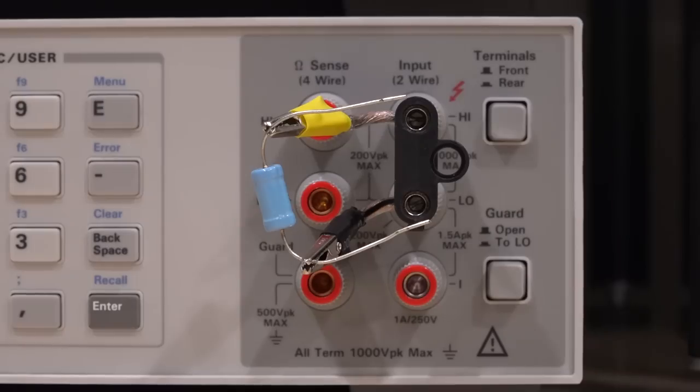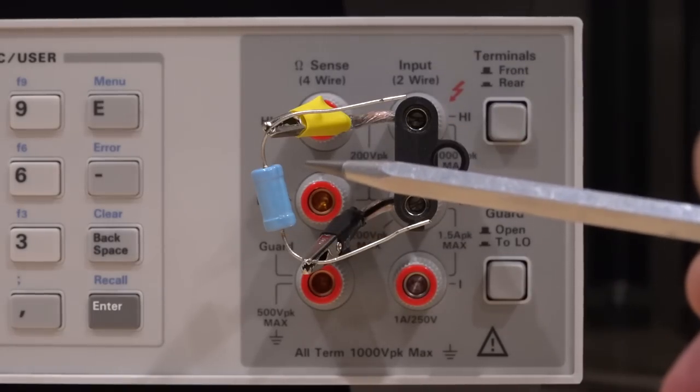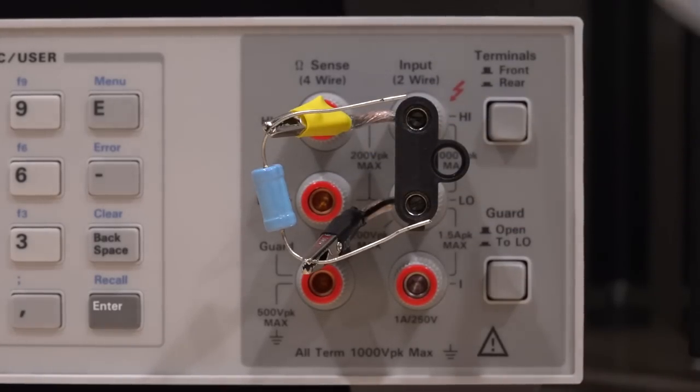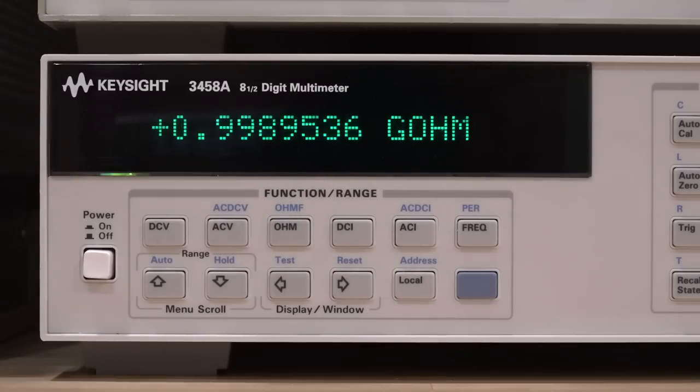Now that we understand it, let's measure something. I have a one-gigaohm resistor — let's see if it gives us anything reasonable. First I'll measure it on a couple of reference instruments using traditional methods to make sure our measurements make sense. Here I have a banana connector going directly to the instrument with the 1 GΩ resistor on two alligator clips. Starting with the Keysight 3458A, the industry-standard 8.5-digit multimeter, and it's reporting 0.9989 GΩ — pretty close to the nominal 1 GΩ value. This is running at 50 NPLC.